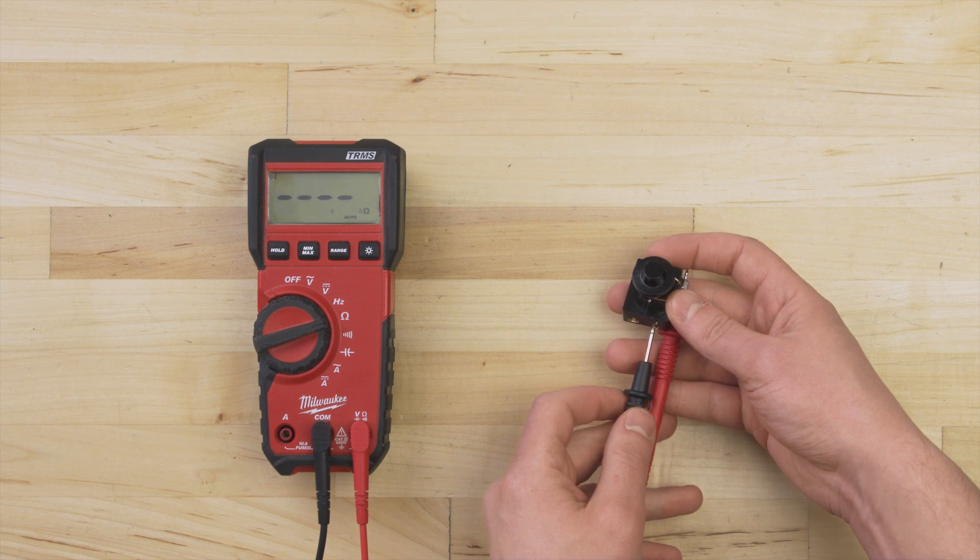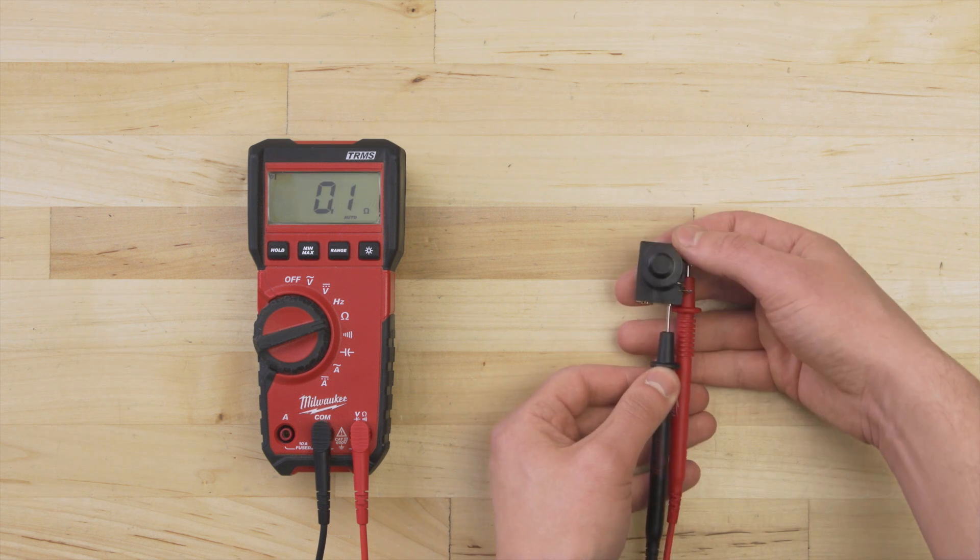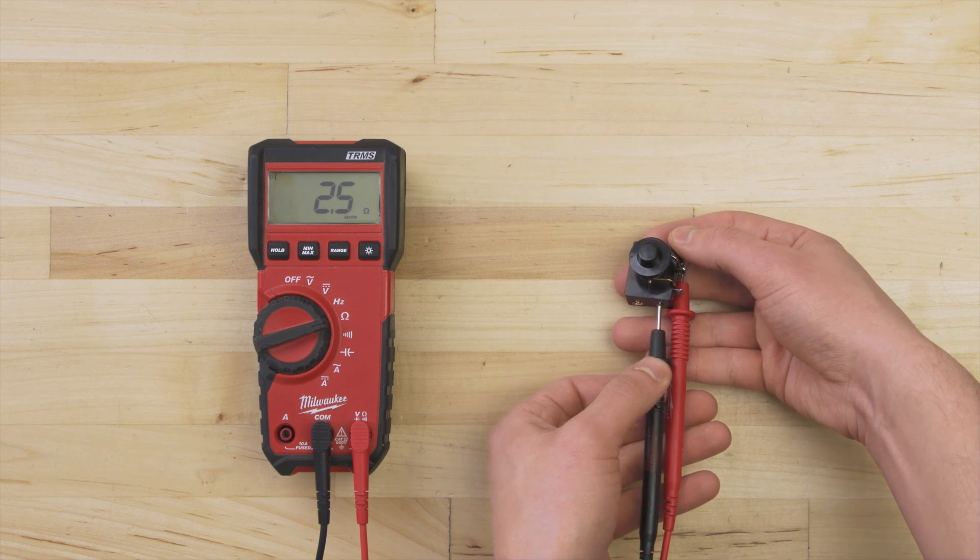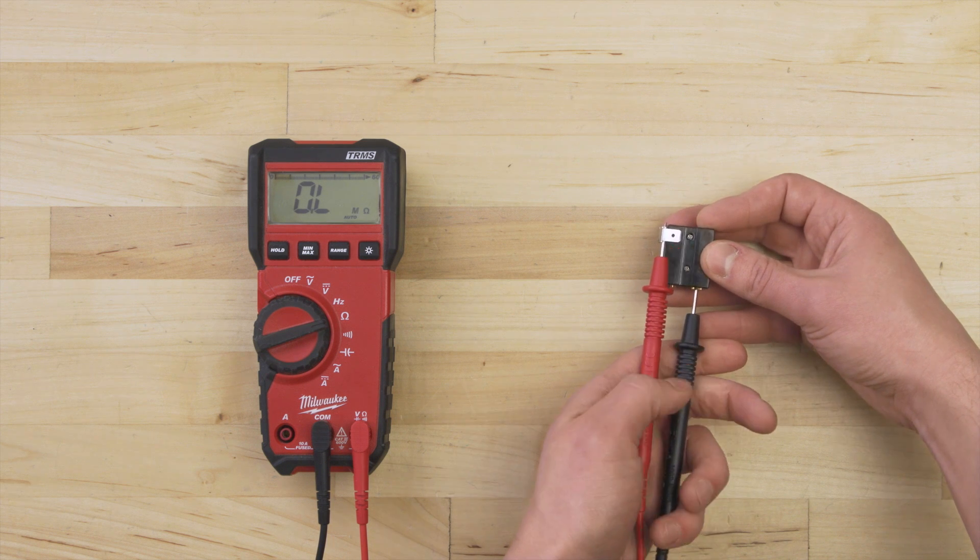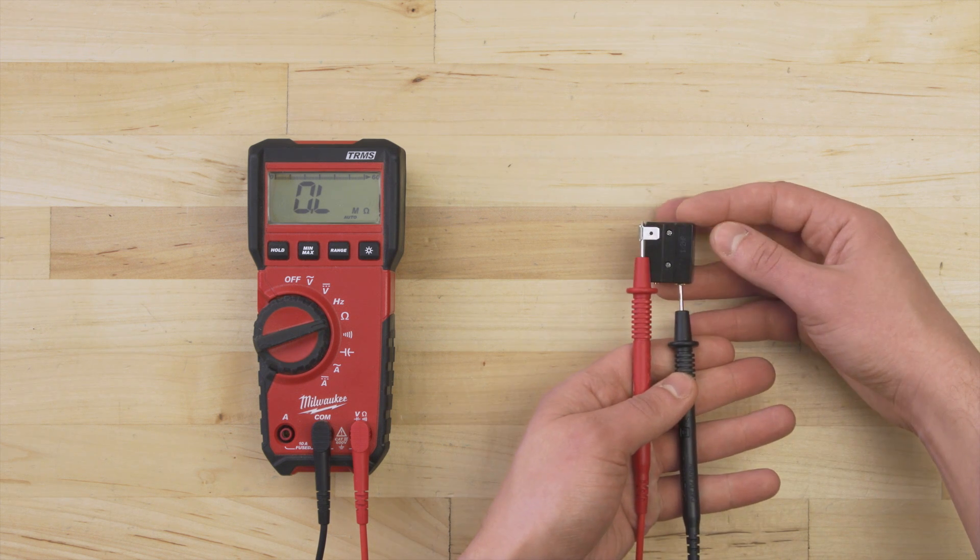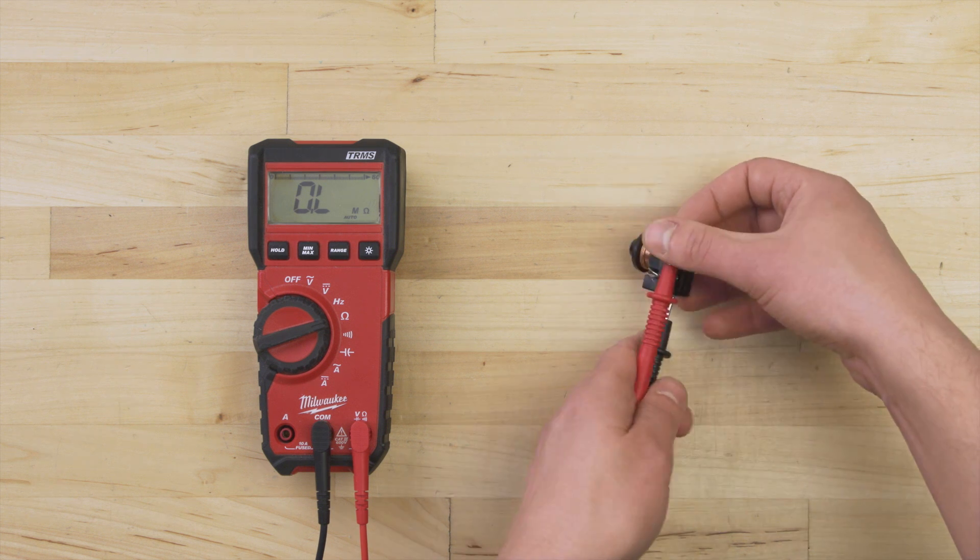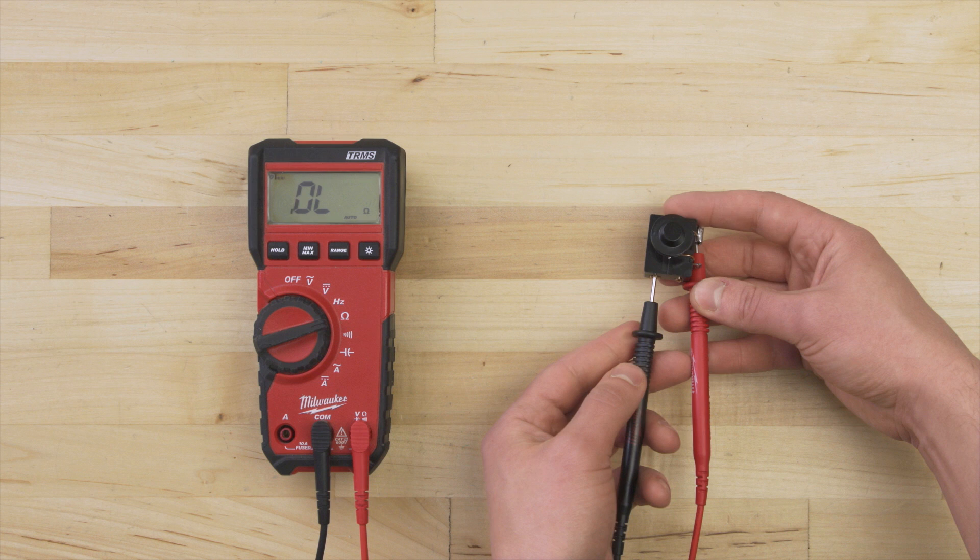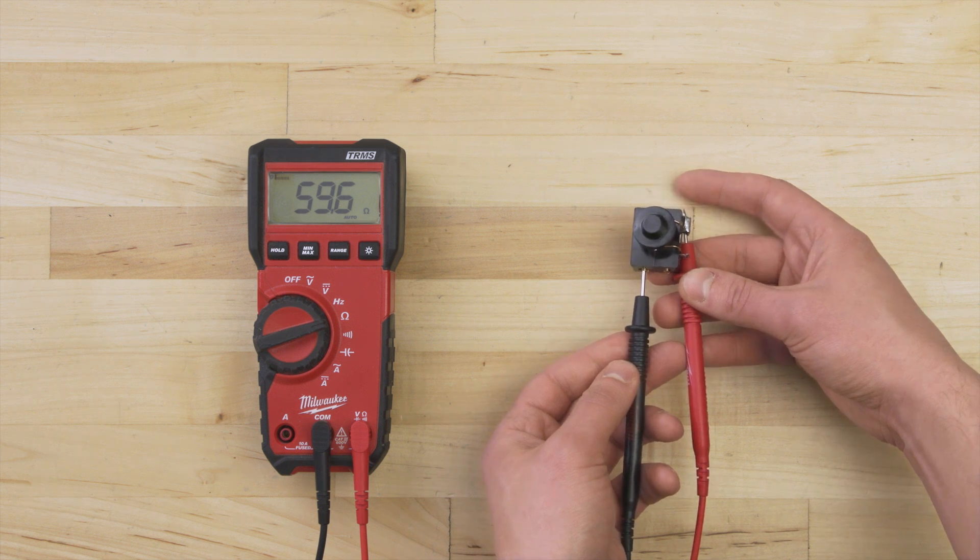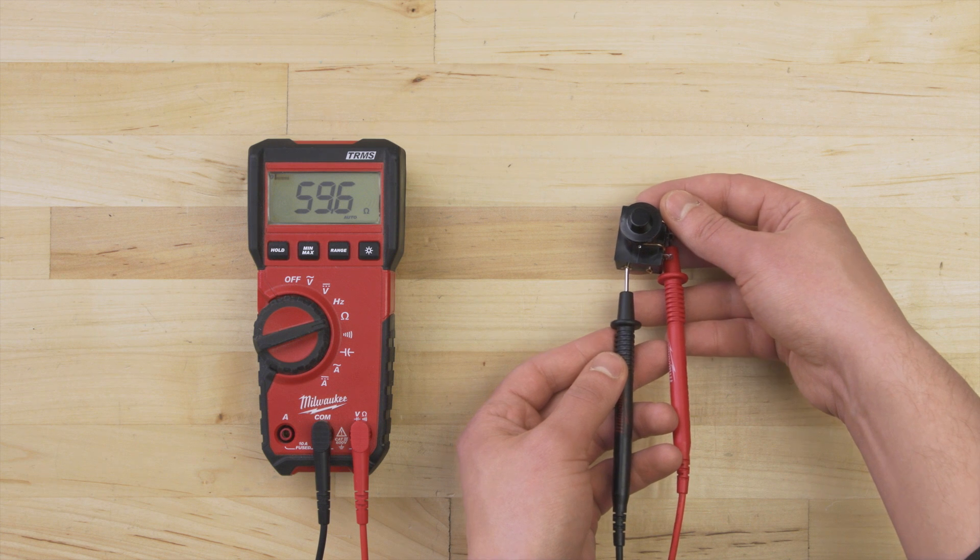For this relay, you'll need to do two continuity tests. First, test between the M terminal and the free terminal. There should be continuity. Now, test between the S and the free terminal. When the relay is facing down, there should be no continuity. When you flip it over, the contacts will close and there should be continuity. If it fails either test, then replace the relay.